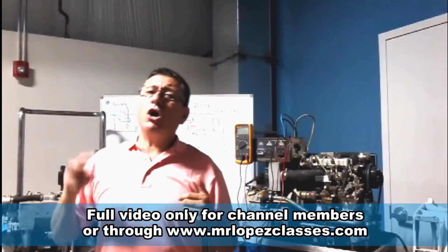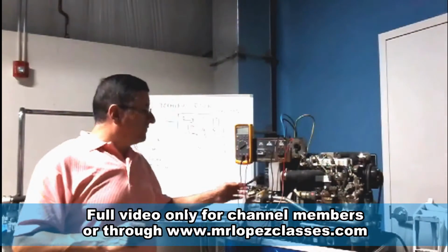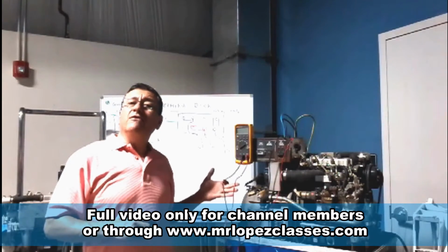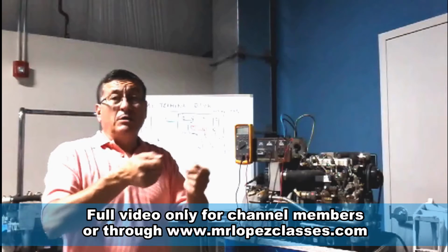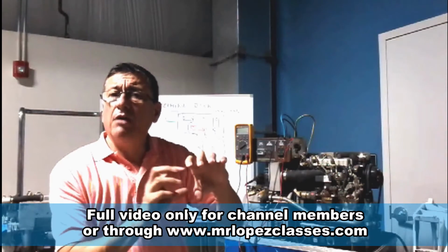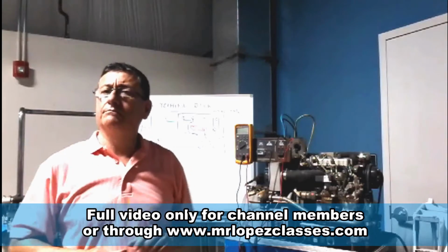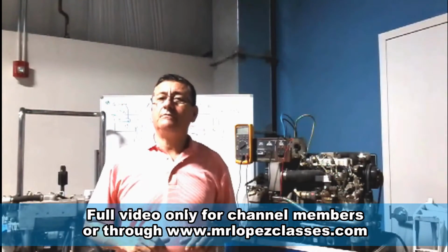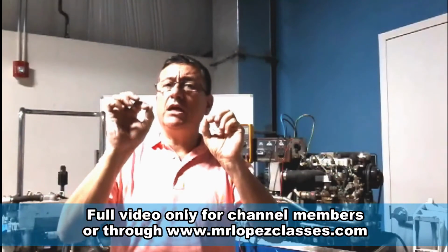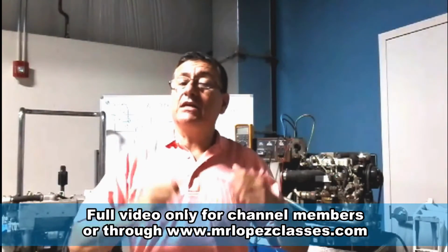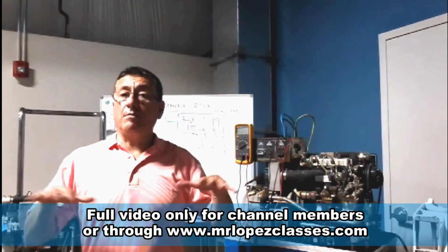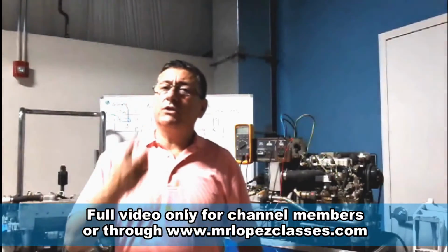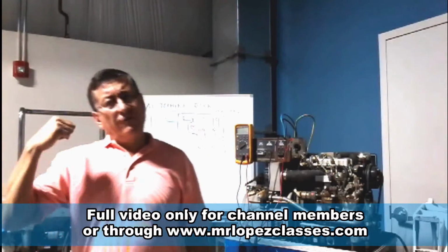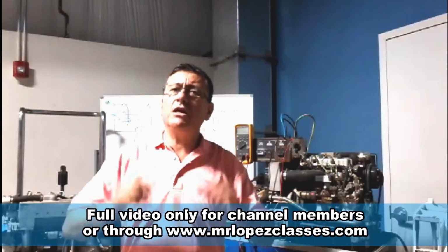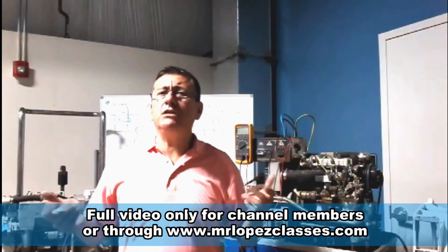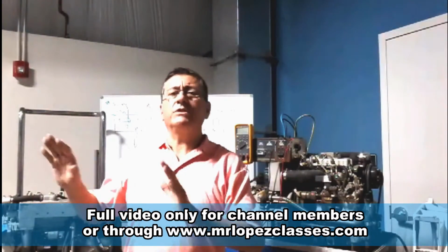The first step is to go to the pedestal and check with the voltmeter the frequency of the pedestal, on the breaker of the pedestal or directly on the outlet of the pedestal, between hot and neutral. Any hot and neutral, and verify that the voltage is 120 and the frequency is 60 Hz. In this particular scenario in America, 60 Hz, 120 volts in each phase. Suppose that the frequency at the pedestal is good. It's 60 Hz, it's 120 volts, 119. In other words, that frequency is perfect.